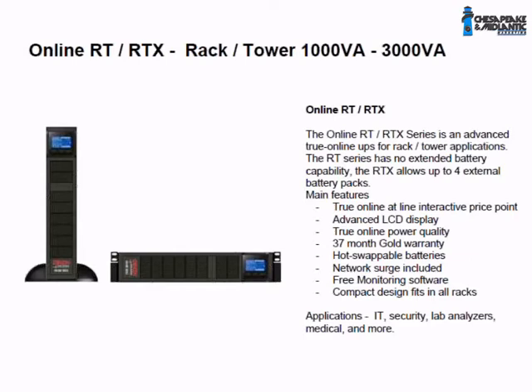So going through the quick features: it's true online, has an LCD display, a 37-month warranty, and a compact design. A line interactive UPS has to have a transformer just by the way they function, which adds a lot of weight. This unit, because it's double conversion, doesn't require a transformer. With a 2 and 3 kVA UPS, these units are substantially lighter, normally 15 to 20 pounds lighter. That's always nice when you're loading something in a rack.